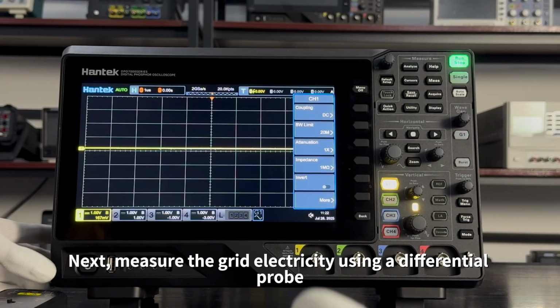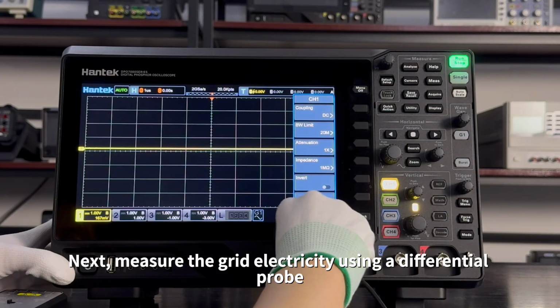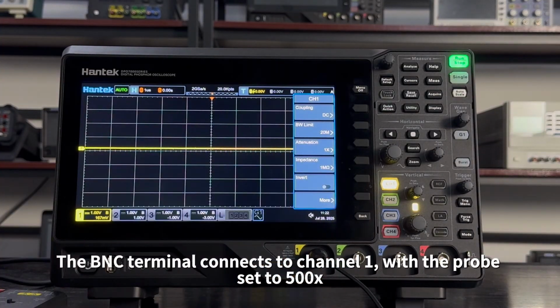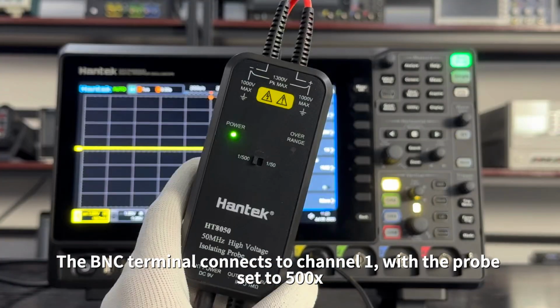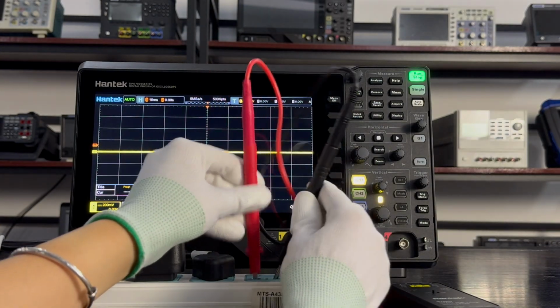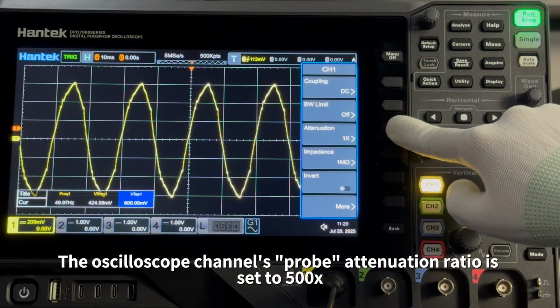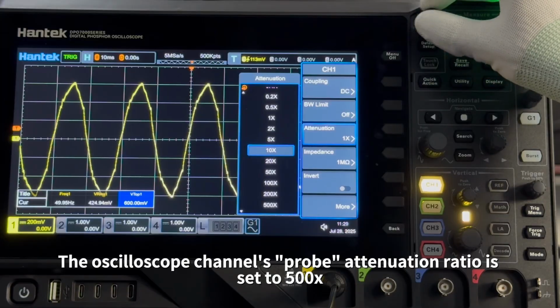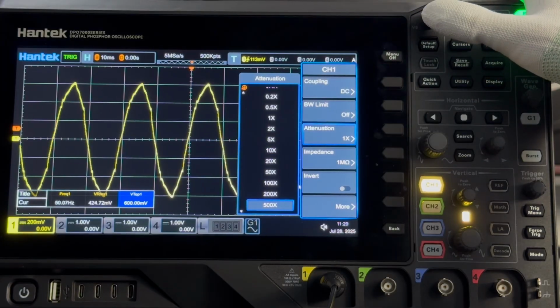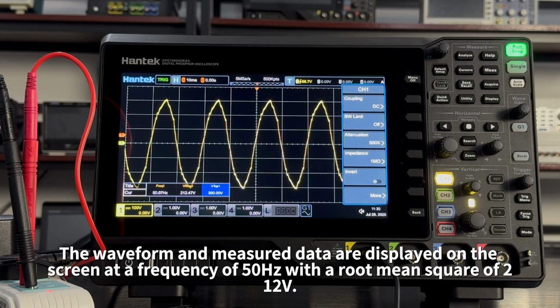Next, measure the grid electricity using a differential probe. The BNC terminal connects to channel 1, with the probe set to 500x. The oscilloscope channel's probe attenuation ratio is set to 500x. The waveform and measured data are displayed on the screen at a frequency of 50 Hz with a root mean square of 212 volts.